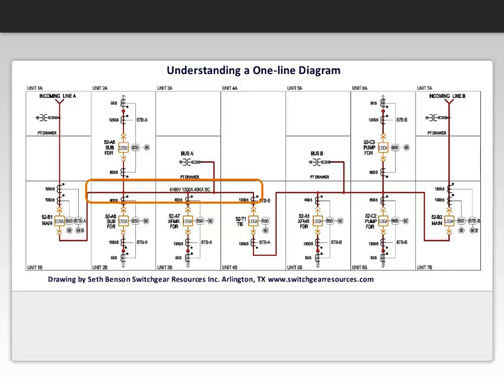It continues to the top of the tie breaker. The flow for incoming line B is similar but ends at the bottom of the tie breaker. Since the tie breaker is normally open, the power flow of incoming line A and incoming line B are isolated. Now, why would this configuration be necessary? The answer lies in having reliability for the plant. Suppose the power feed from the utility is lost on incoming line A. On a conventional lineup, the plant would be unable to operate.